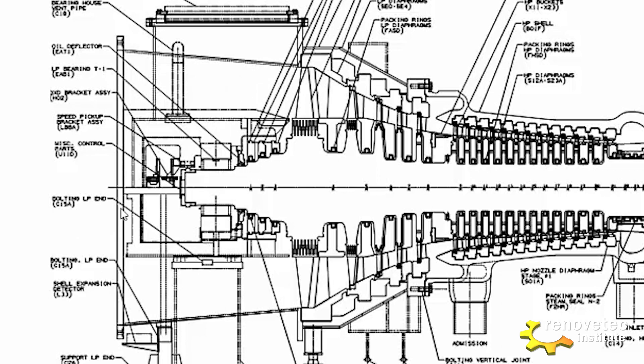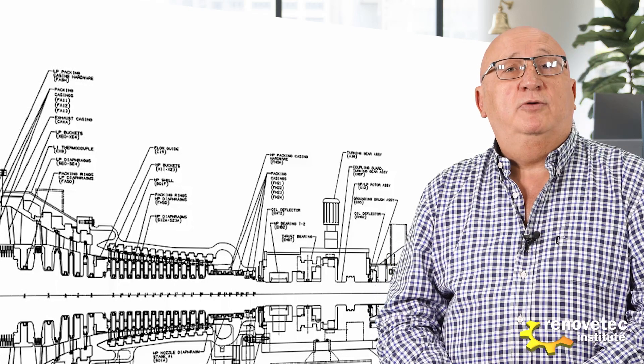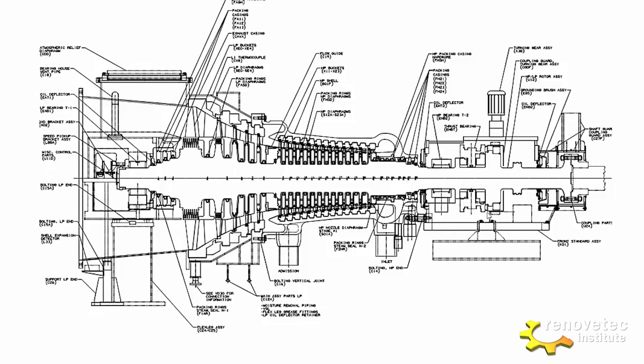At the outlet, we have different instruments to detect problems in the shaft. For example, we have a proximity sensor to detect the movement of the shaft in the axial direction, and another sensor to measure the eccentricity of the shaft — to measure if the shaft is bent or not. We can also see the different supports of the casing. This support is fixed — a fixed point. Remember that when the turbine is cold it has one size, but when hot it is bigger. The expansion of the casing goes from this direction toward the outlet, so this support is flexible and this one is fixed.